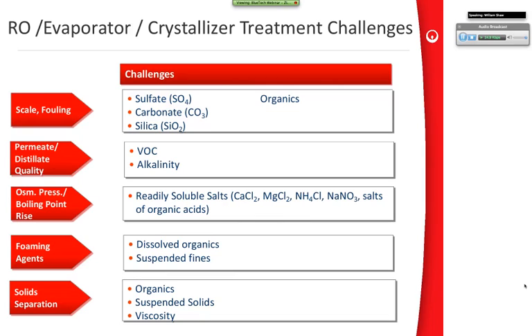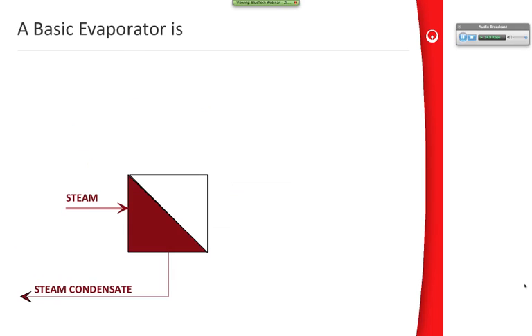What are the things we worry about? Again, in ROs, evaporators, crystallizers, we worry about scaling and fouling. We worry about organics carrying over into the distillate or other volatile components. We worry about osmotic pressure and boiling point rise because that determines the amount of energy we have to put in. And then we worry about things like foaming and how difficult it is to separate the solids out.